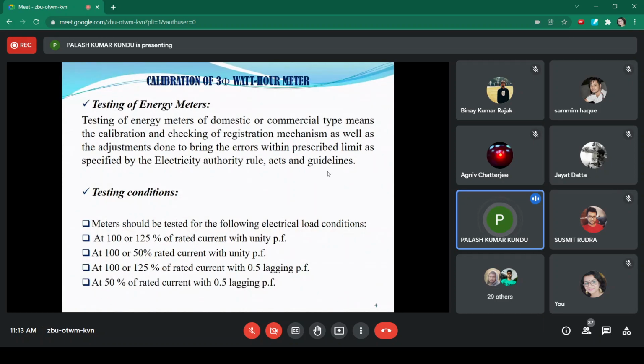The registration mechanism consists of a number of elements, that is a decade dial system. Each may cause its own error. So there is another type of error which may be caused by maloperation of the registering mechanism. So in effect there are two types of error which will occur cumulatively, and the gross error will result in an error in the kilowatt hour measurement. That means the testing of the energy meter is to check the calibration and to check the registering mechanism.